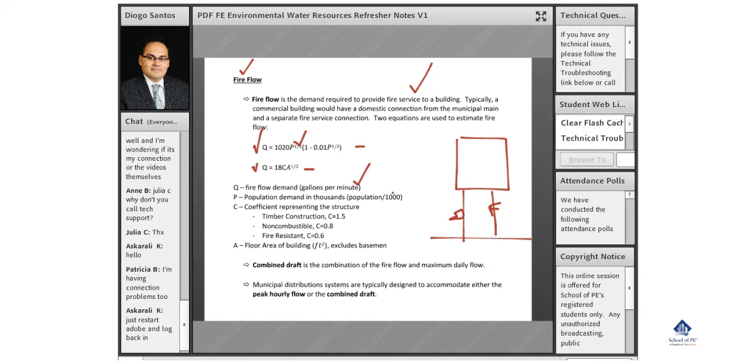The second equation is for building design. Fire flow demand equals the coefficient C representing what type of structure—whether timber, non-combustible, or fire resistant. Numbers are higher for wood construction, then non-combustible like concrete and steel, then fire resistant with extra protection. The flows go down the more protected your building is.